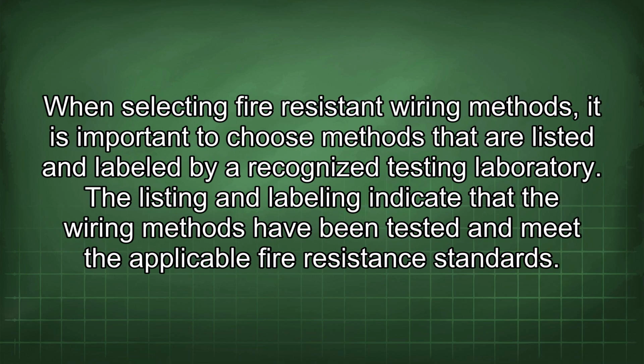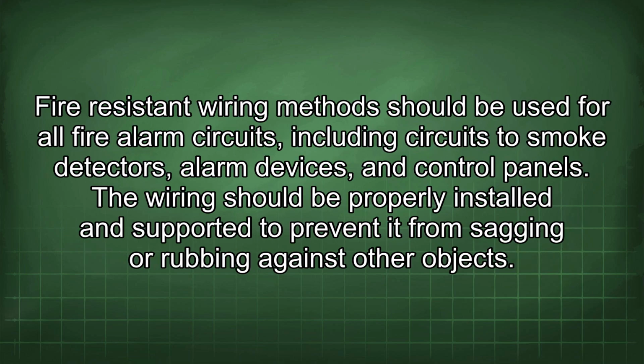When selecting fire-resistant wiring methods, it is important to choose methods that are listed and labeled by a recognized testing laboratory. The listing and labeling indicate that the wiring methods have been tested and meet the applicable fire resistance standards. Fire-resistant wiring methods should be used for all fire alarm circuits, including circuits to smoke detectors, alarm devices, and control panels. The wiring should be properly installed and supported to prevent it from sagging or rubbing against other objects.